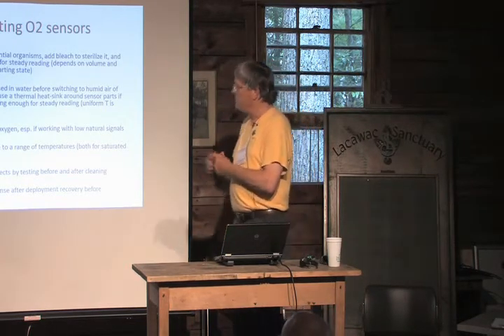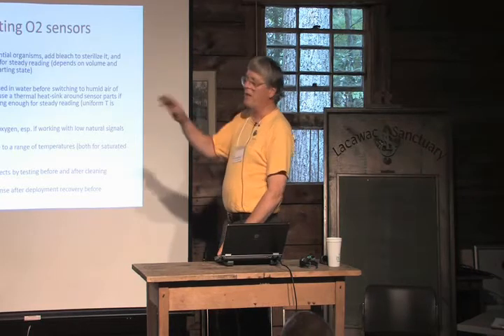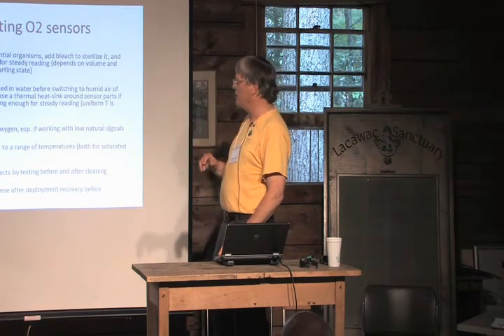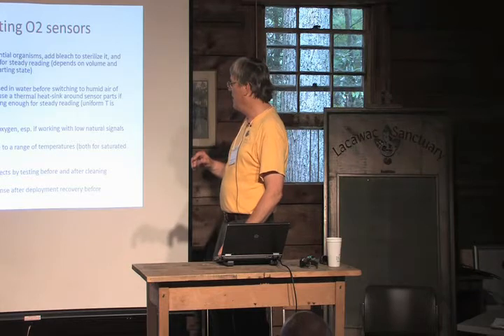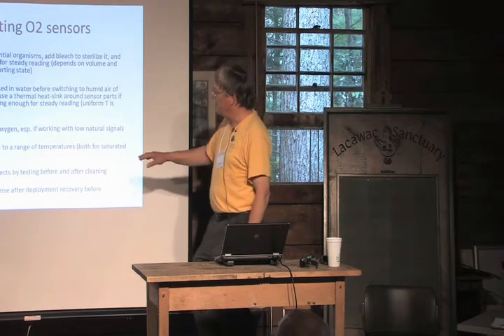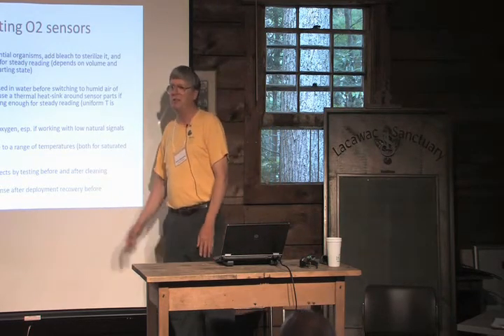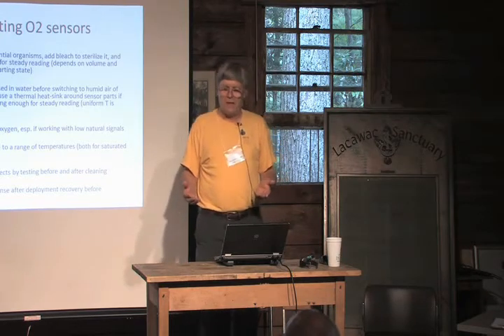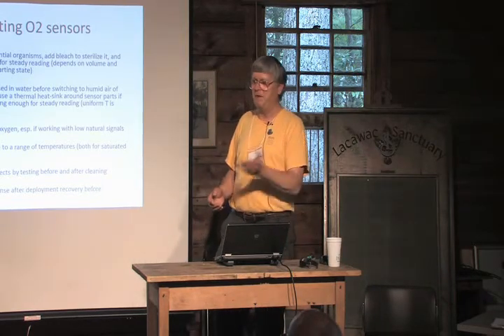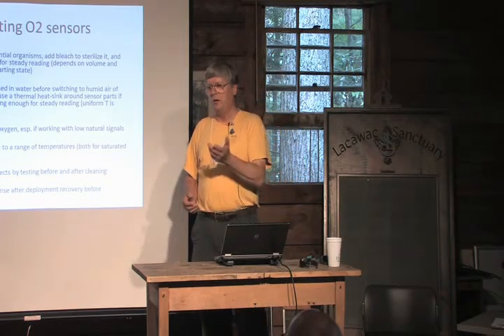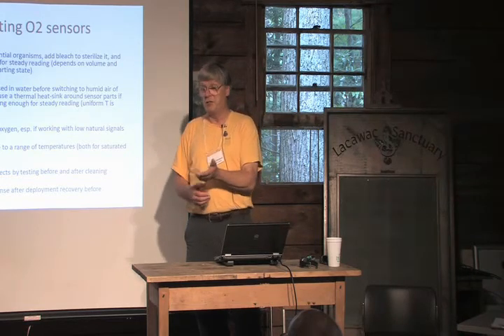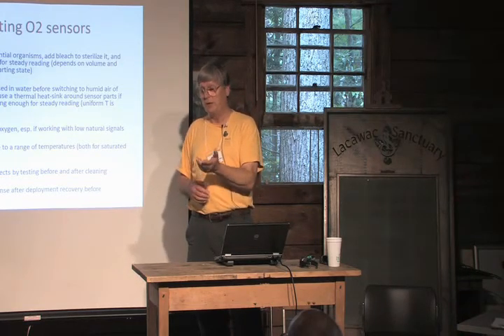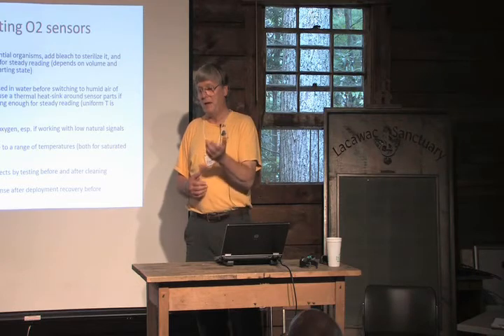I'm going to skip over the advice. We can talk about this in the demo afterwards, where I will show you how we're going to do some calibrations. But I will say that for testing the biofilm effects on a sensor, the simple approach is to bring your sensor back from the field where it's been deployed, put it uncleaned into a calibration chamber, whichever one you prefer, but it's worked best in water.